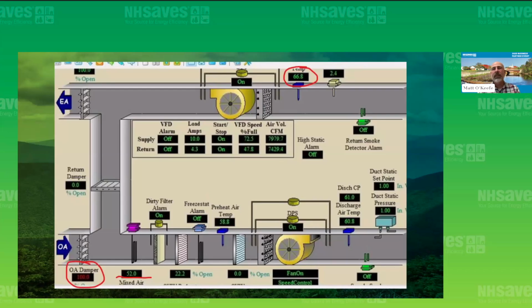Another one is a site where we found an outside air damper disabled to run wide open. So instead of utilizing some of the warmer return air that it has available, it has to heat the cooler outside air all the way up to the supply temperature set point that it's maintaining fine. So again, you're not going to find anybody that says, hey, this isn't working right in the building, because they're getting the temperatures they want. But if you look at this system, you'll see we should be using as much of this return air as we can, so that we don't have to heat this outside air.